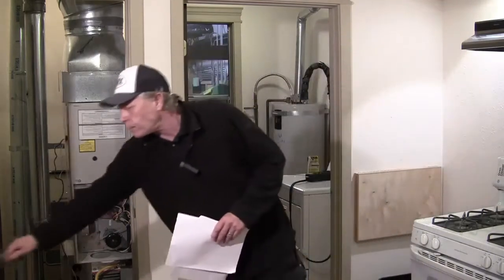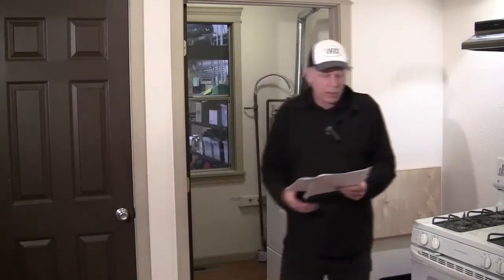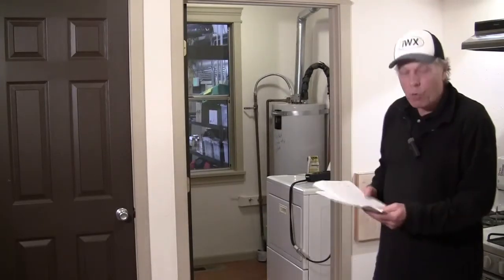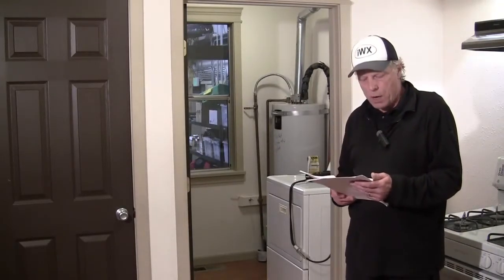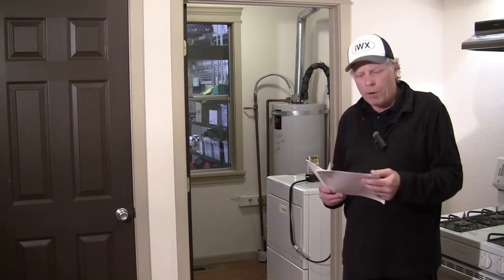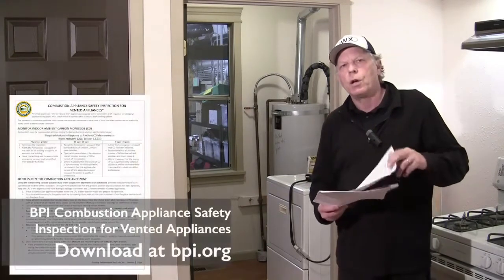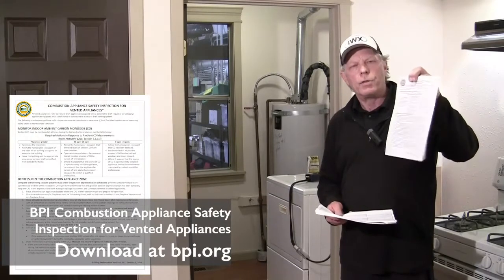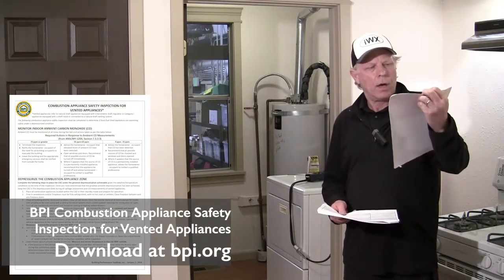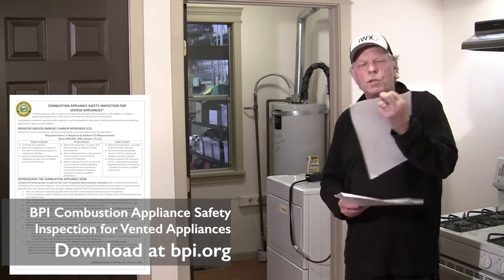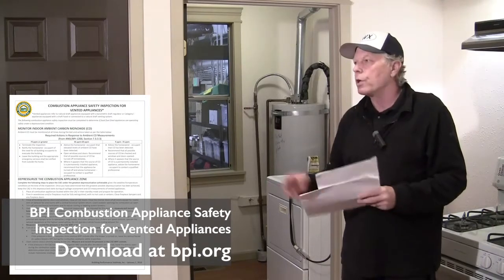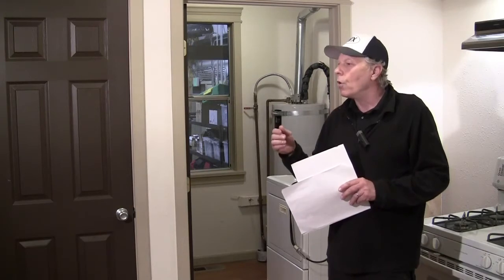All right. Okay, now we want to set up the home. Line number 1 says set up the home for CAS testing, and I'm going to use my BPI sheet here that I got from BPI to give me some guidance. It's called the Combustion Appliance Safety Inspection for Vented Appliances. And we're going to start with making sure we've got all our exhaust fans turned off and all of our appliances on standby. We also will close windows and doors to the exterior.